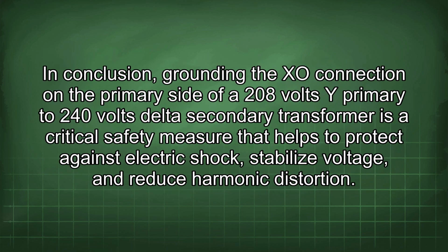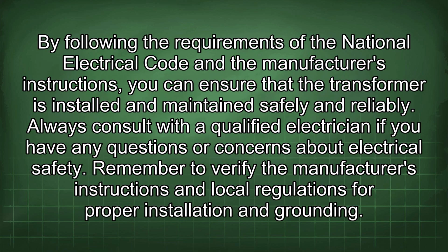In conclusion, grounding the X0 connection on the secondary side of a 208 volts Y primary to 240 volts delta secondary transformer is a critical safety measure that helps to protect against electric shock, stabilize voltage, and reduce harmonic distortion. By following the requirements of the National Electrical Code and the manufacturer's instructions, you can ensure that the transformer is installed and maintained safely and reliably. Always consult with a qualified electrician if you have any questions or concerns about electrical safety.